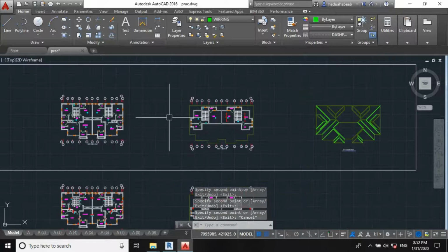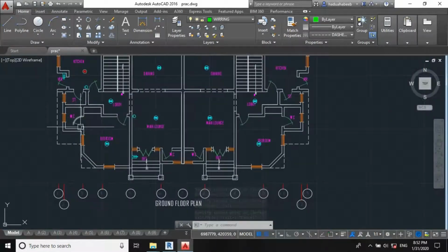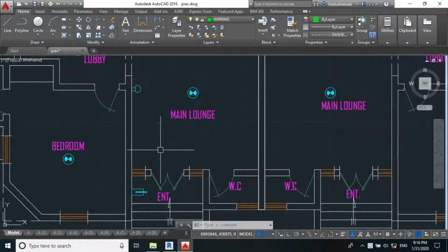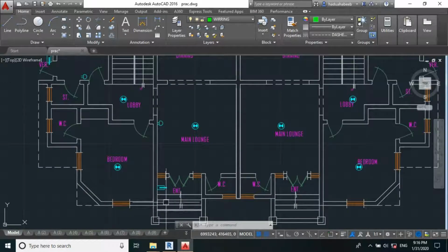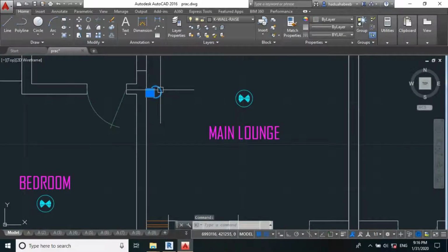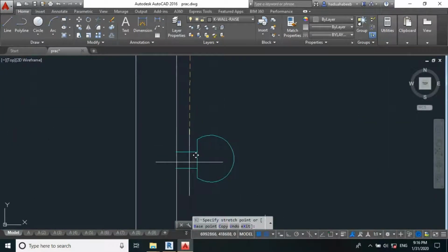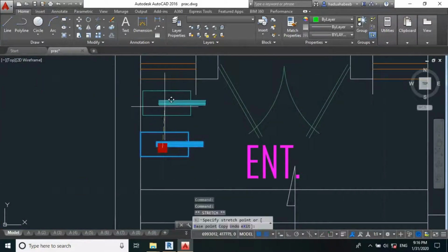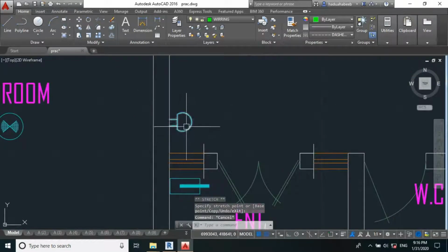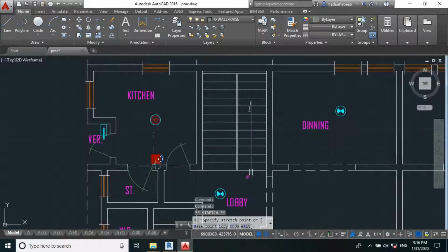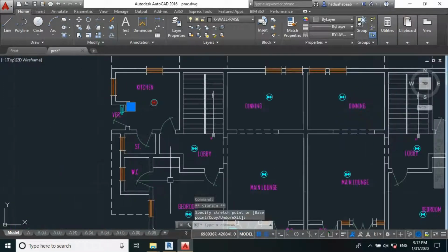So, having designed that, the next thing is to coordinate our bell with our call point, which is the break glass. And to achieve this, we'll rather try to have an emergency break glass, which implies our control panel won't be included. Because of that, I'll be moving this break glass close to the bell, so that we can have a direct connection from this glass to the bell, which implies this one will be emergency break glass. And for our kitchen too, since we have the same opportunity, we can place our break glass here too. So it will cover for this area, likewise for the corridor.